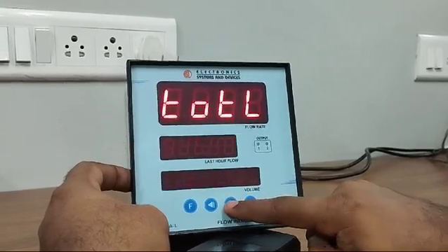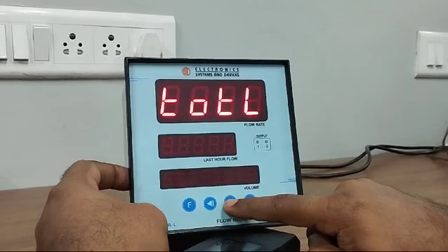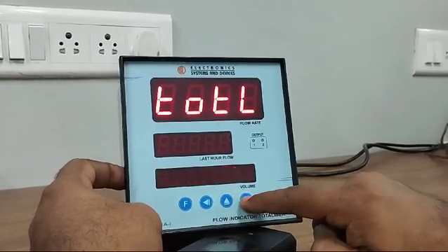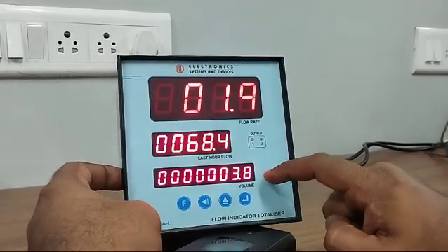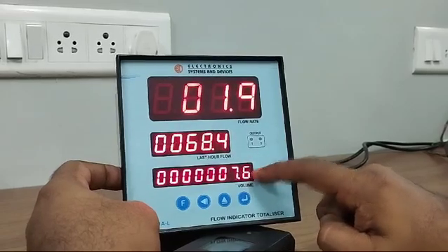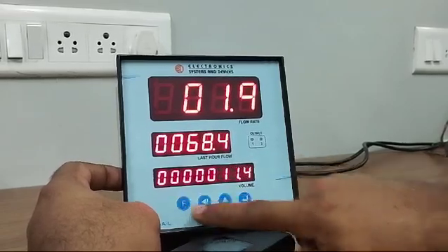The next is resume or pause. If you want to pause the totalizer, you can keep it pause. I will keep it resumed. Now the 0 and started counting from beginning.